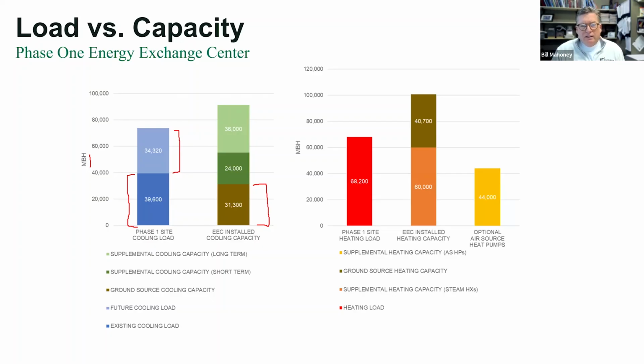What we need to do then to meet our load, this wouldn't even meet our peak cooling load today. We needed to add some supplemental cooling for the phase one work, and then follow-on work. Once this cooling gets added, we need to add more capacity in more supplemental. So what this told us was even that big athletic field that was available to us, it looks relatively big, it still wasn't enough to meet the current load and nowhere near enough to meet the load if all those buildings were air conditioned. And then the same thing happens here on the heating side.